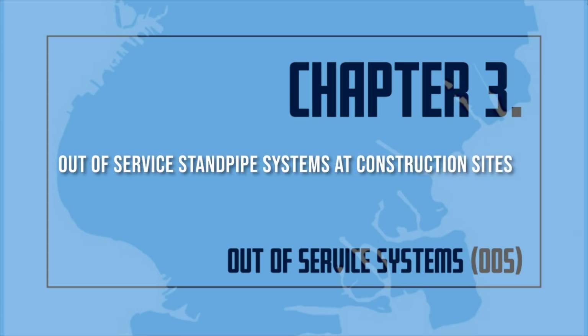Out-of-service standpipe systems. At construction sites, the owner/fire safety manager and/or impairment coordinator shall immediately notify the fire department of any unplanned out-of-service condition and comply with the requirements for an unplanned out-of-service condition. 1. Immediately notify the fire department of any unplanned out-of-service condition and otherwise comply with the requirements of Fire Code Section 901.7.4. 2. Notify the fire department at least 24 hours prior to any planned removal of the standpipe system from service and otherwise comply with the requirements of Fire Code Section 901.7.3.